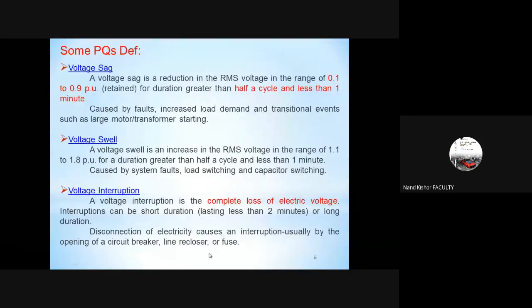We move to the next slide here. Now, on this slide, we have the definition for power quality. So, in reference to the voltage signal, this is how we define it. Reduction in the RMS voltage, which could be in the range of 0.1 to 0.9 for a period lasting more than half cycle, and up to a period of 1 minute. So if you have a dip, that means a sag in the voltage of this range, 0.1 to 0.9 for this much duration, it will fall in the category of voltage sag, and it is caused by faults. You can have increased load demand, or there could also be transitional events like starting of a large motor or the energization of a transformer here.